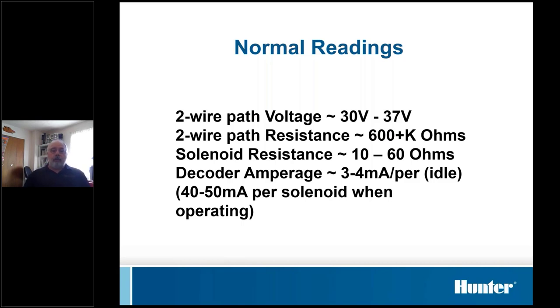As far as decoder amperage, when it's connected to a controller and running off the normal voltage, it's 3 to 4 milliamps per decoder idle when they're not operating. When they are operating, it's 40 to 50 milliamps per solenoid. So if you've got a decoder running two solenoids, it's going to be close to 100 milliamps for current draw. Those numbers change dramatically when we go over using 24 volts. But as a rule of thumb, each decoder on the controller should draw about that. You can use that and look at the current draw on the controller to try to get a gauge on health.